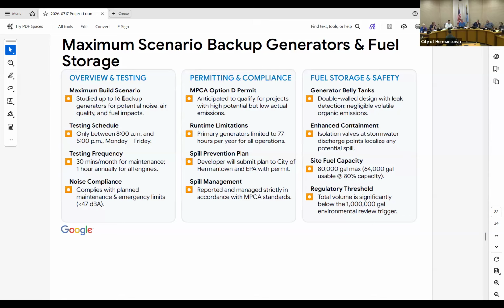So you talked about a spill plan. Will the diesel be stored in self-containment so it doesn't contaminate outside if there's a spill? Yes, the belly tanks hold the required volume, and there's an additional double-walled containment so that if the initial wall were to break or leak, a secondary wall keeps that same quantity within the unit.